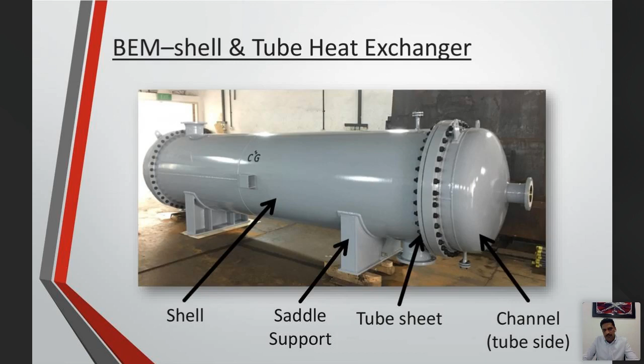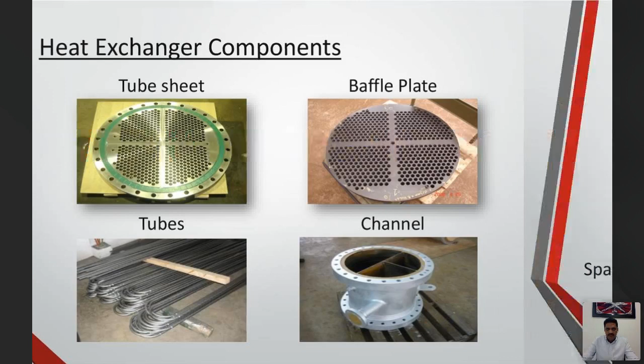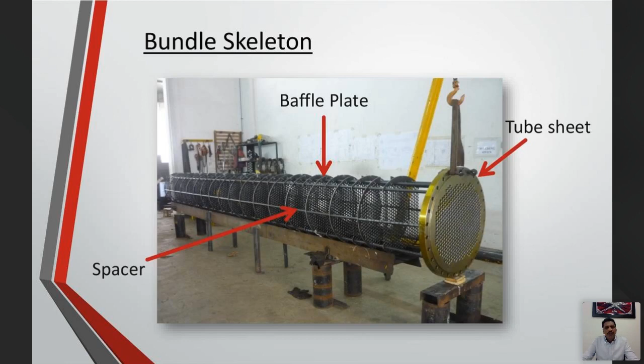These are all the heat exchanger components. It's called tube sheet, where the tube holes are. Tube holes are made, and the tubes will pass through this tube sheet. This is the baffle plate, where the heat exchanger skeleton is made. This is the support plate. This is tube. This is a channel cover. This is the first point of assembling the heat exchanger. It's called bundle skeleton. We put the tube sheet on one side, and we spread the baffle plates with the help of spacers, so the skeleton is getting ready before putting the tubes onto the bundle.